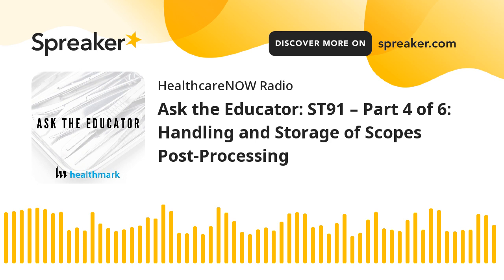Lifting a scope out, the outside is wet and the inside is wet. As far as the drying that needs to occur, it's active filtered forced air drying. We need to incorporate newer technologies made to deliver filtered forced air at a certain pressure. A lot of people assume they can just take an air gun and point it at the proximal end of a channel and call it good—but you've only dried the port and the first part of that channel, not all the way down. So what we're talking about are tabletop or wall-mounted options made to deliver air at the appropriate pressure for a minimum of 10 minutes: pressure-regulated forced instrument air or a minimum of HEPA filtered air.